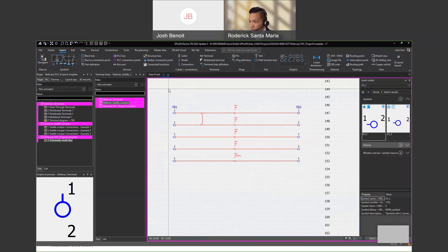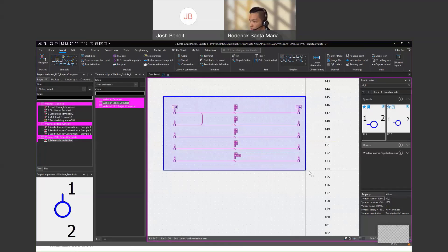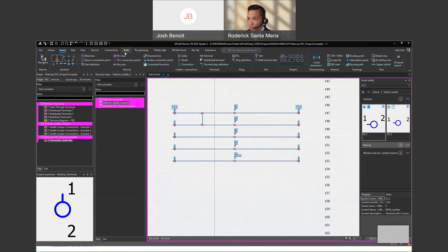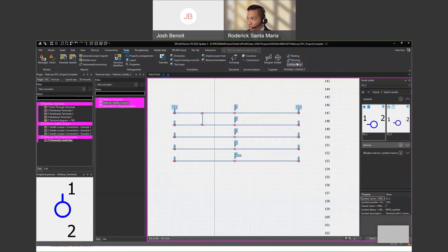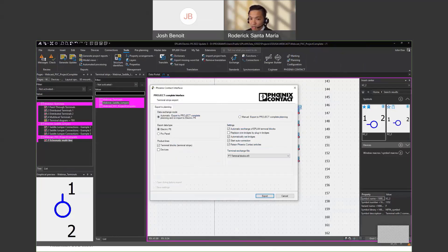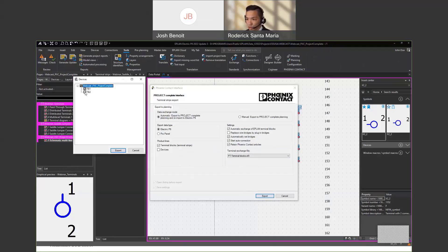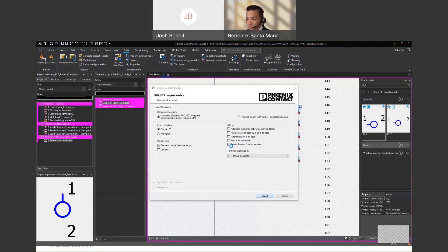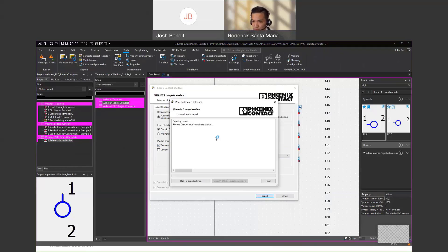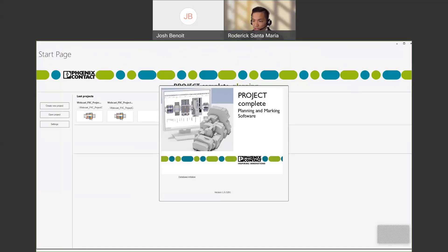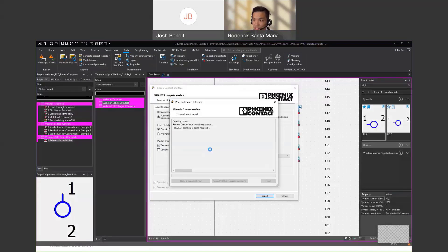Now what I'm going to do is select all the items that I have in the schematic and go to Tools > Phoenix Contact Planning. I'll be using the default settings and all I need to do is hit Export and choose both terminals, so that it'll configure it within the software. What's happening in the background right now is it's simply trying to figure out how you configured your schematics, and then it'll assign part numbers and add accessories to your terminal blocks.